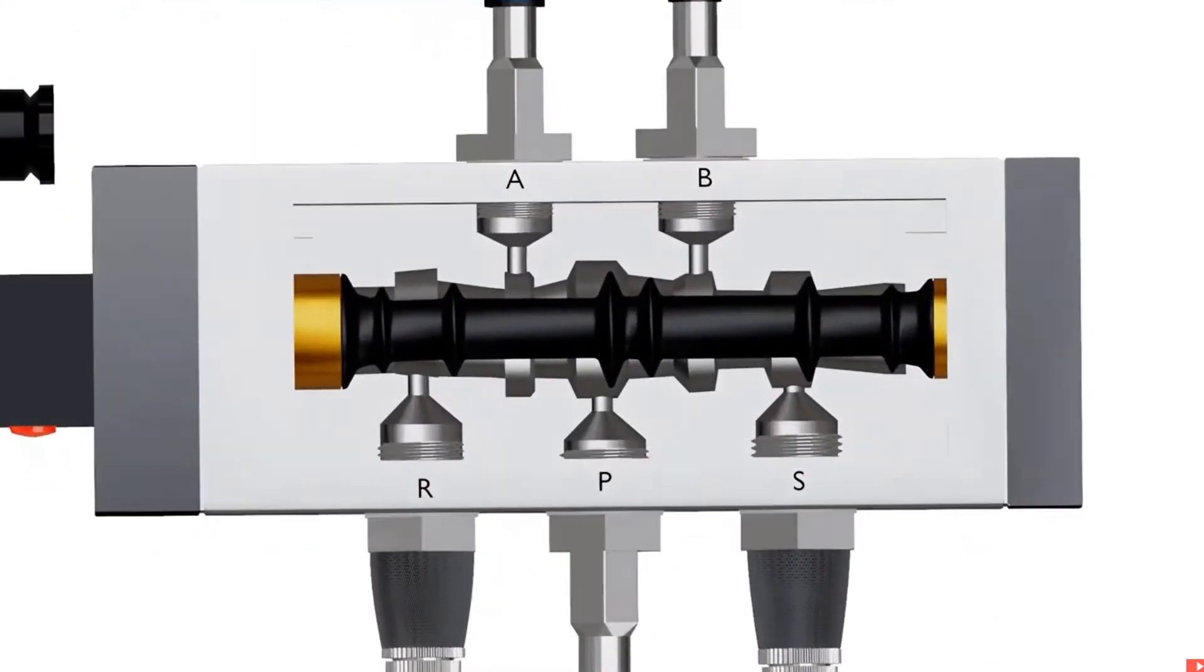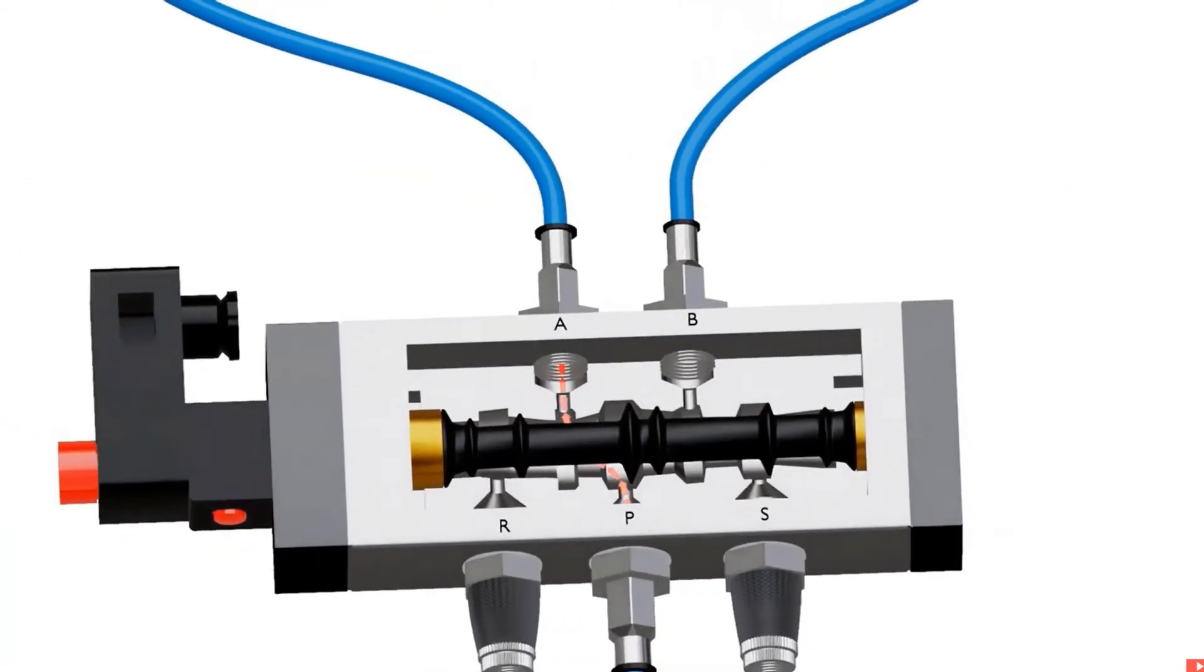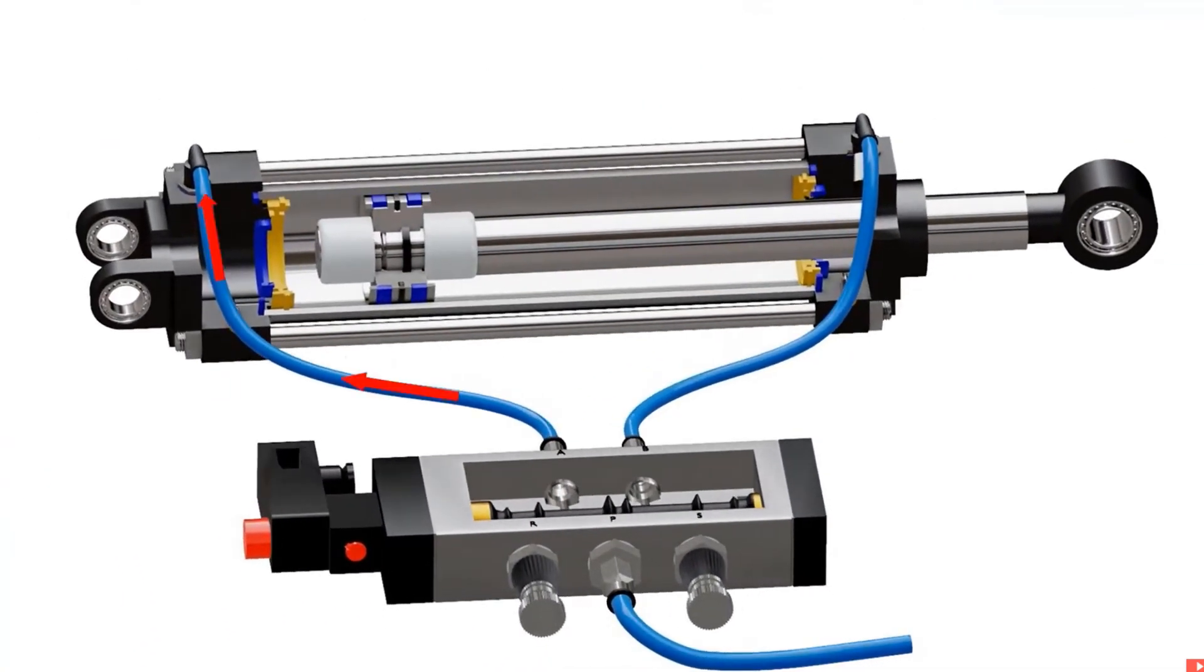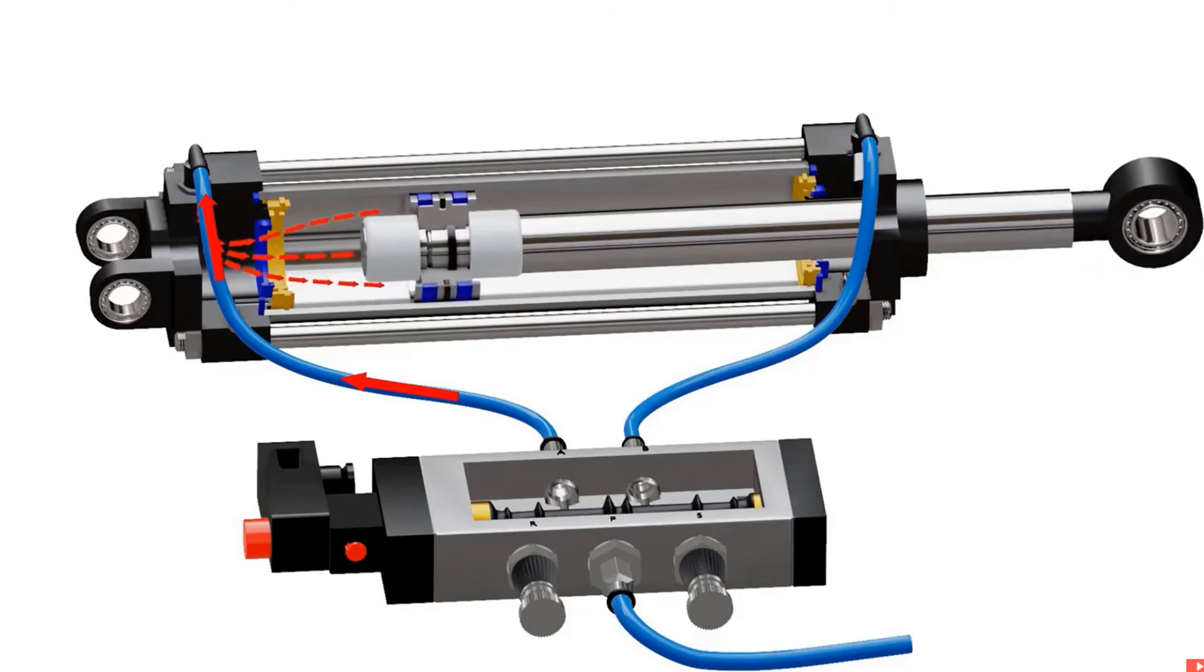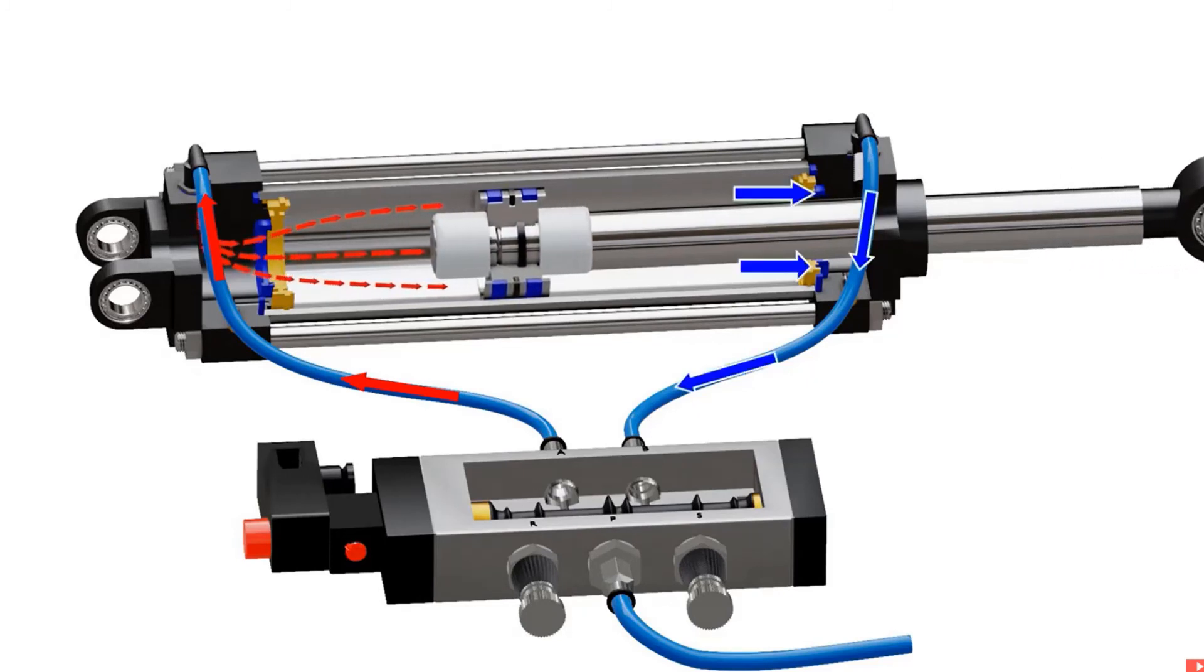Now let's understand how a pneumatic cylinder works. The compressed air is supplied through inlet port P of the valve. The valve directs air to a particular direction which we can observe in the animation. In this case, the air is directed to port A. This high pressure gas is then transferred to the cap end of cylinder through the pneumatic hose. This creates high pressure in the cap end of cylinder which therefore pushes the piston towards the head end. This also pushes gas from the head end.